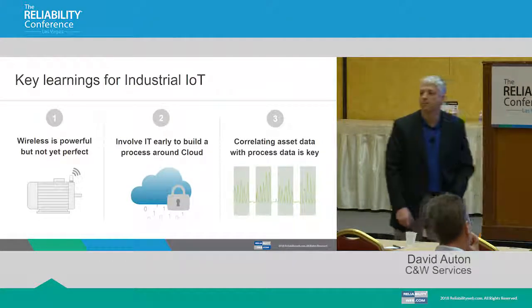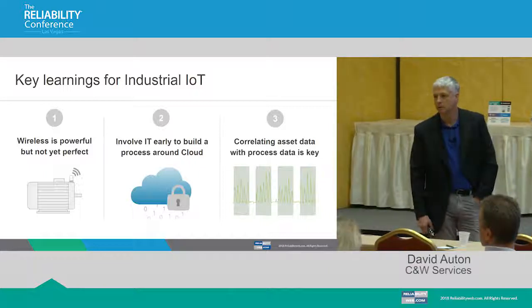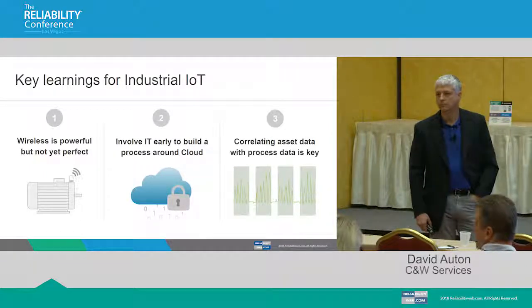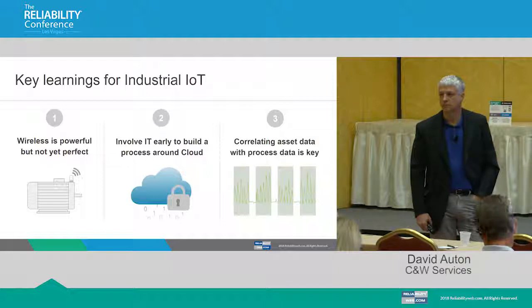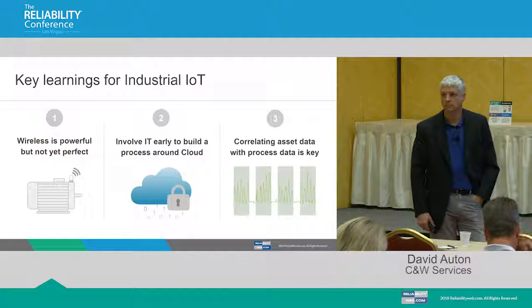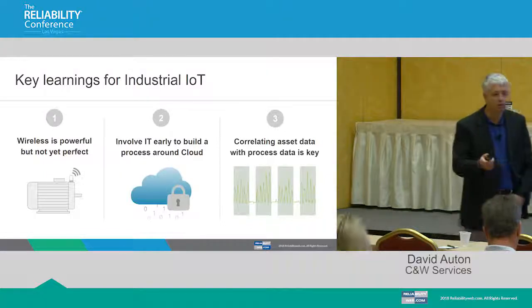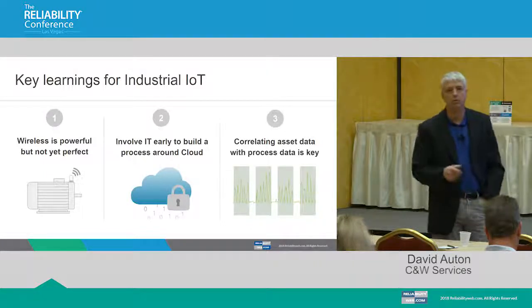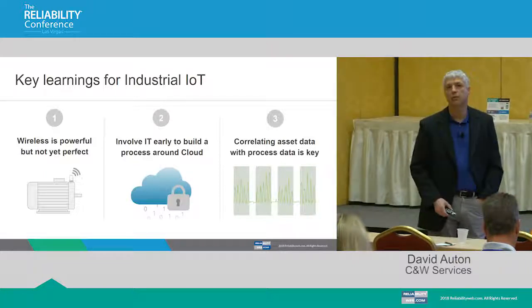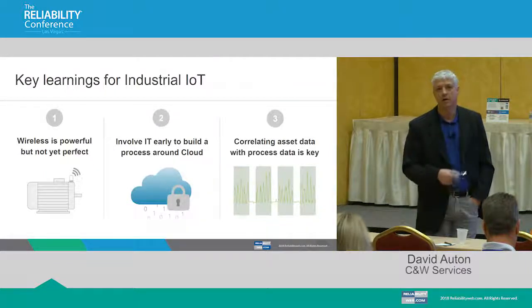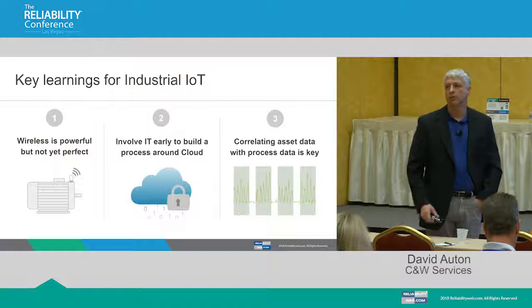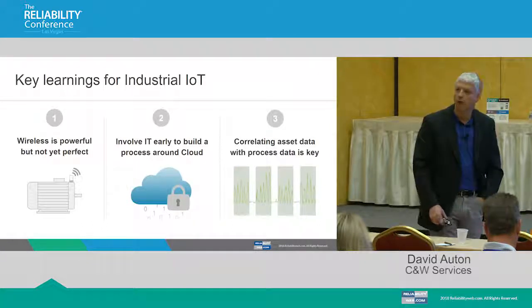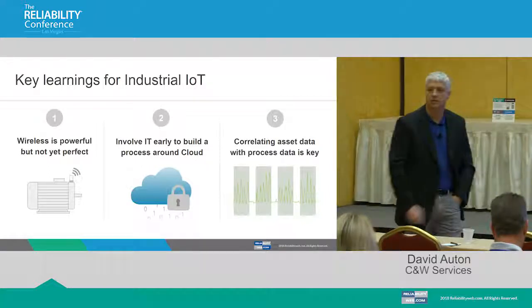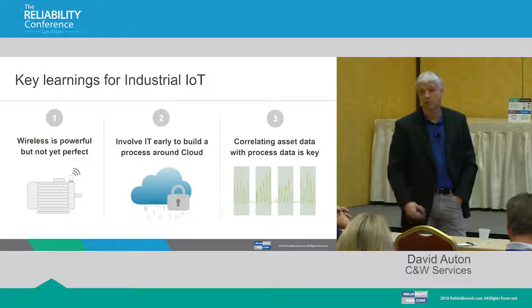Decisions for them. Yeah. In terms of return on investment, have you estimated how much you are reducing your failure rate as part of the implementation? Almost all the ones I've priced where you just use the vibration monitoring with the alarm conditions, and you don't necessarily have consultants reading those on a regular basis, less than a 1-year ROI based on average failure rates is usually what I get. So the prices come way down, and so it's very cost competitive.